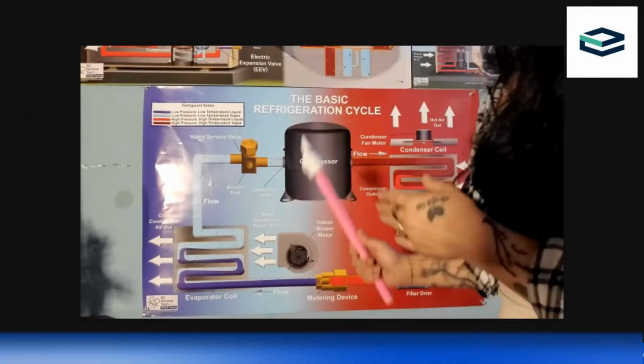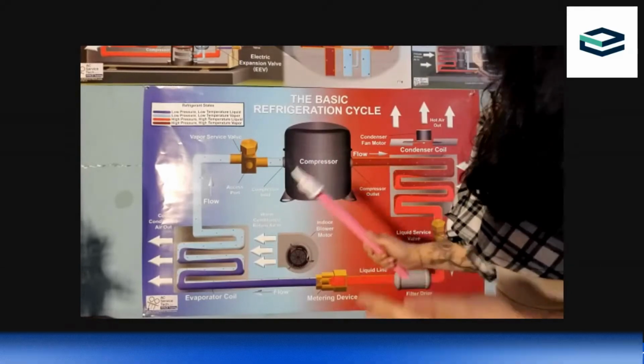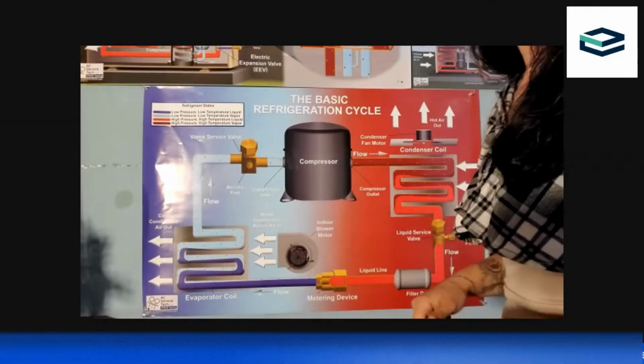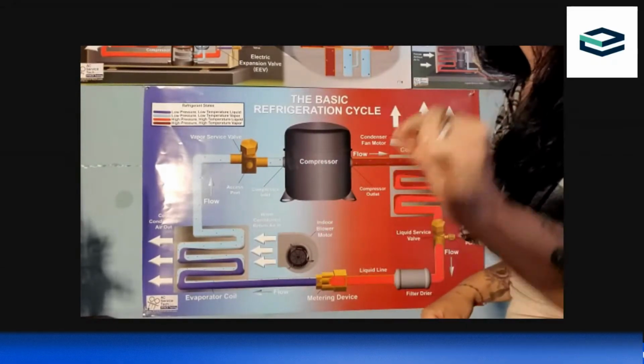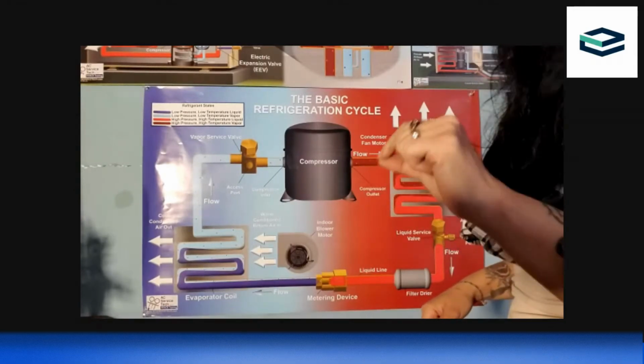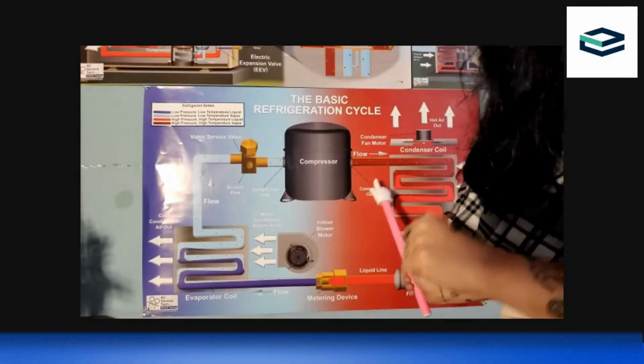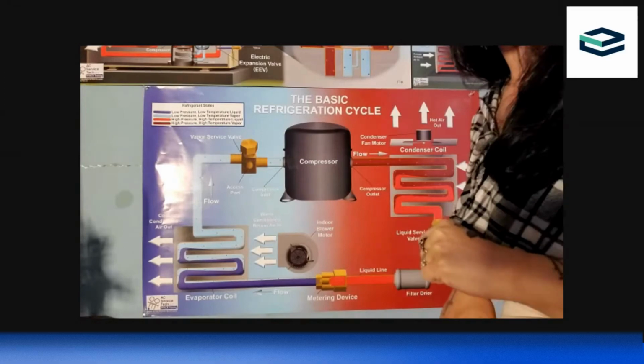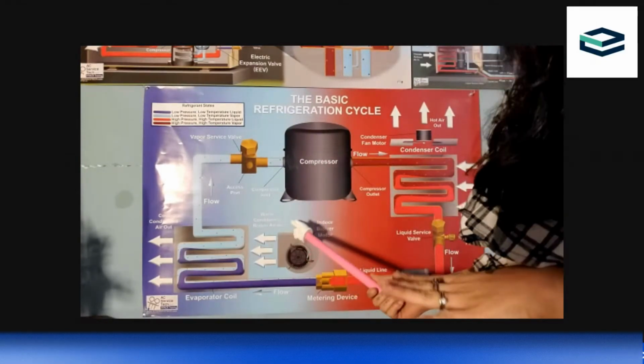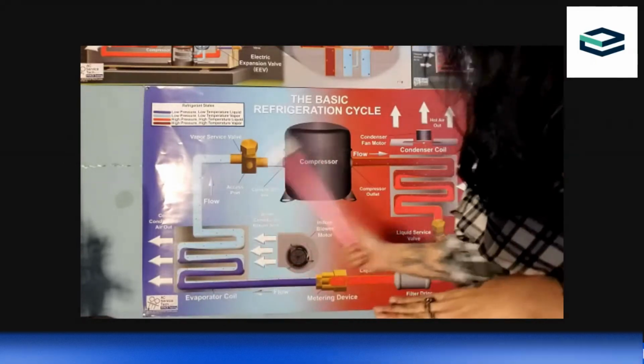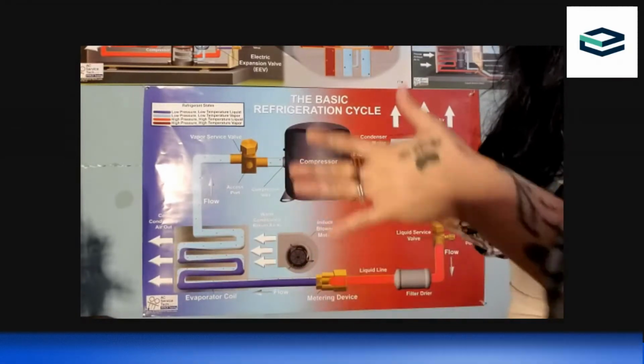And if it's working within that spectrum, these are not critically charged units. By critically charged, I mean it has to be the exact, to the gram, bit of refrigerant. These are relatively wing it and ding it charge systems. So you can dial it in using your gauges. You can dial it in knowing what your liquid and vapor saturations are, what your superheat and subcool are, but it's never going to be the same for every system.